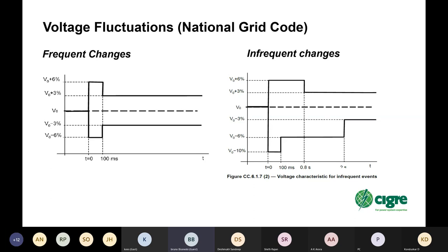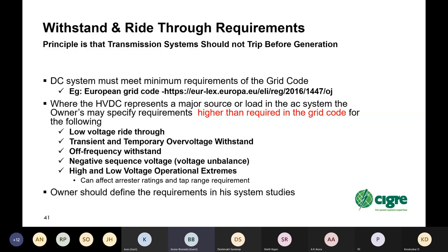And now just looking at some typical performance requirements that are specified, in this case, for voltage change on switching or other events. You see that for infrequent changes, the system impact can be larger or longer than for frequent changes. Withstand and ride through requirements are very important, especially if the DC is providing capacity. The DC system has to meet, as a minimum, the requirements of the grid code. And in some cases, the grid code is a mandatory requirement, even a legal requirement, such as the European grid code. And I've left you a link there to have a look at a typical requirement.